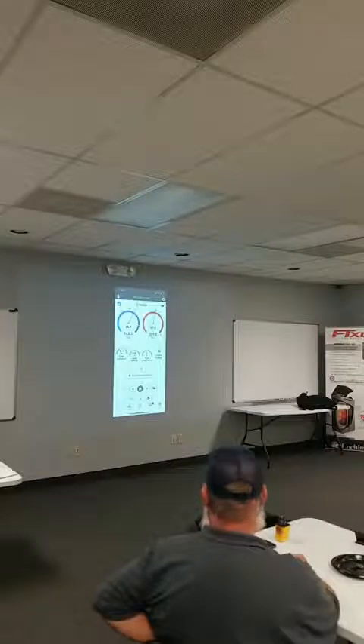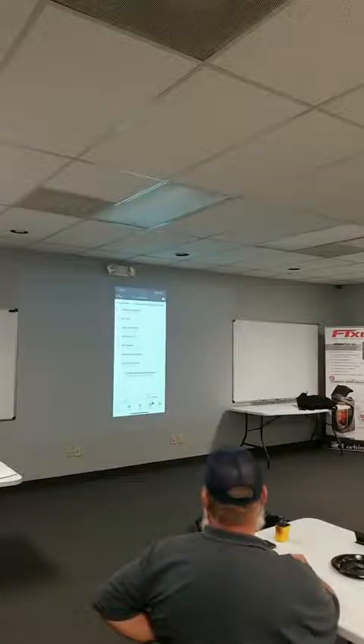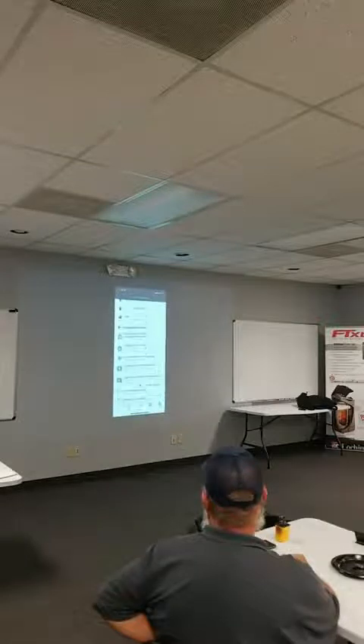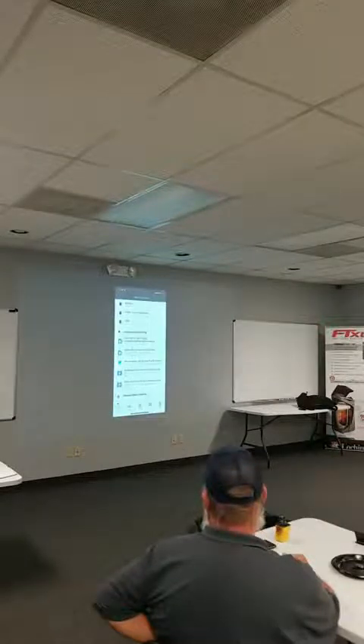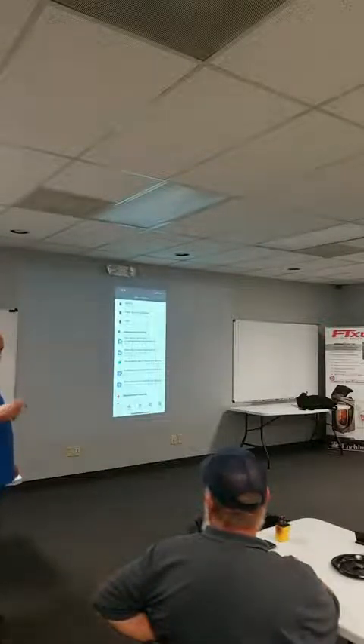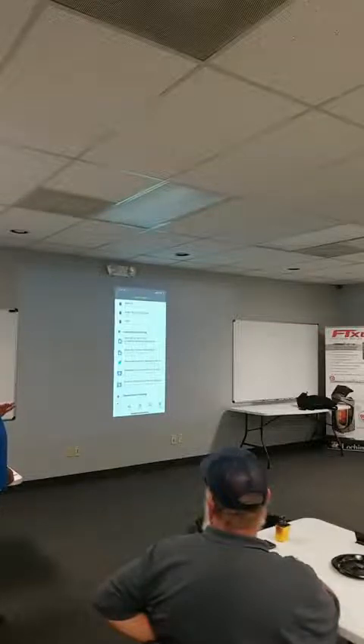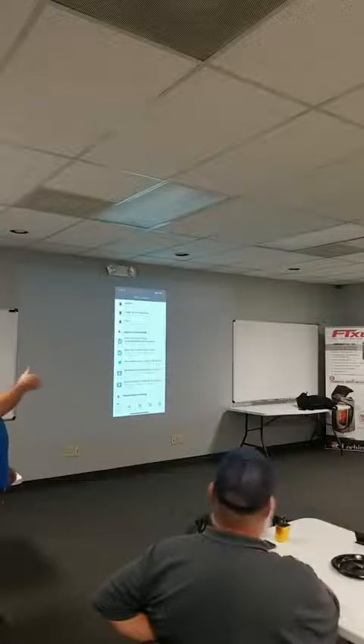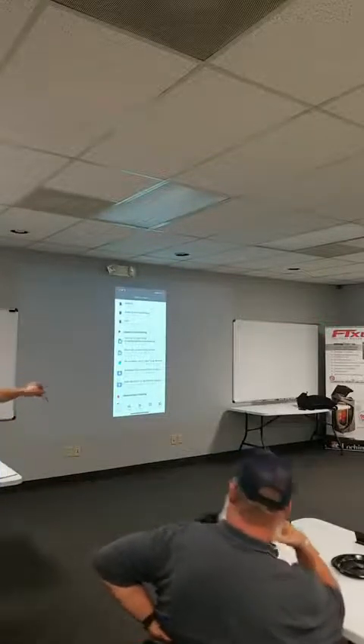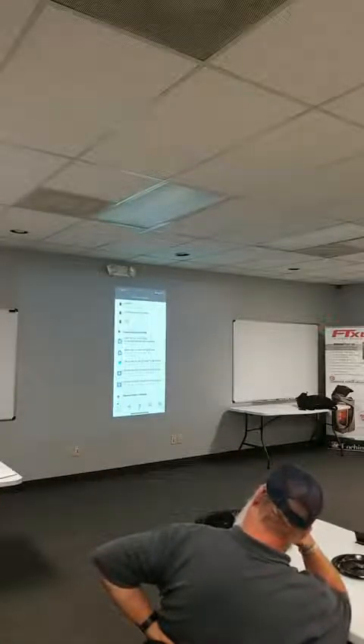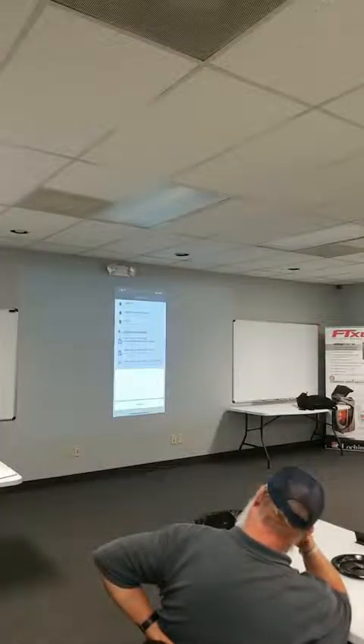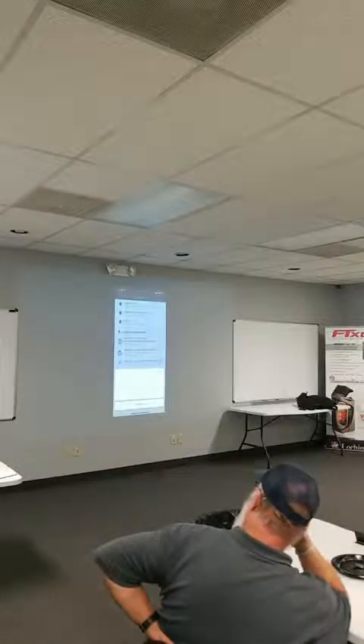In your profile. So when you set up your project, let me just exit this project. Down here, there's 2 things. There's multi-stage and multi-circuit. Multi-stage means it's one refrigeration circuit up to 4 stages. Usually it's only 2, but with variable refrigerant flow, we're allowing people to capture it at 30%, 50%, 75%, whatever they want. Multi-circuit means there's more than 1 circuit of refrigeration. So when you select multi-circuit mode, you select the number of circuits, and then you could have 2 sets of probes, and you could map them for suction pressure to liquid pressure to suction, whatever you want.